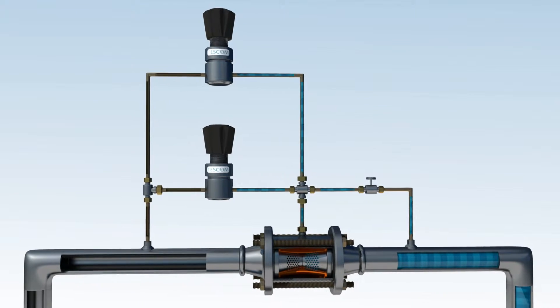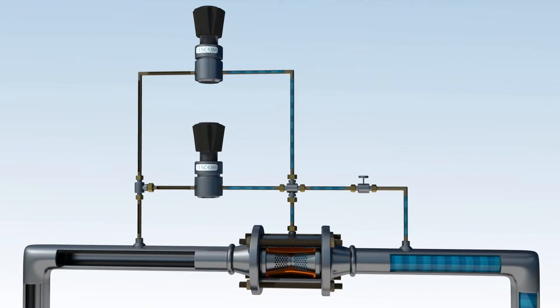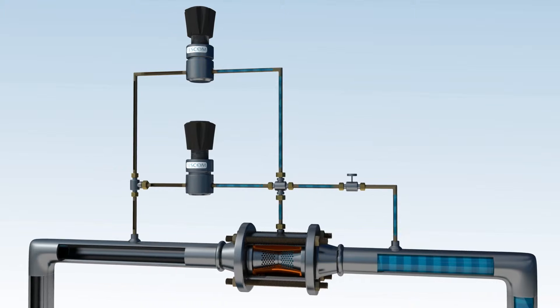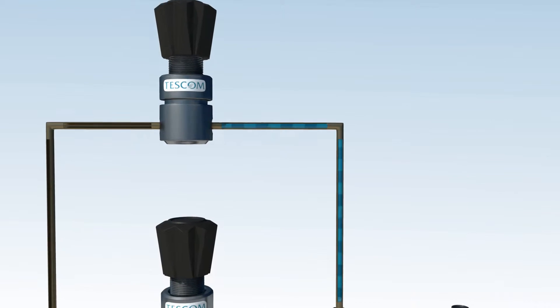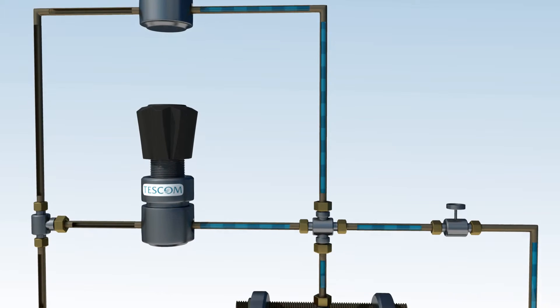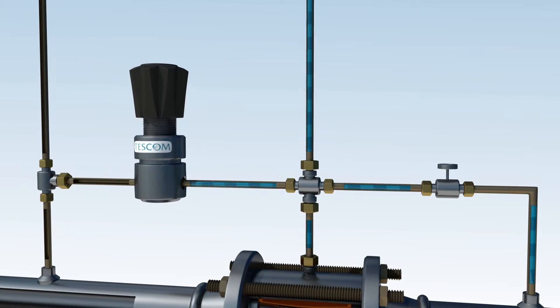SureFlow's design can control both with one valve by using a back pressure controller and a pressure reducing controller. The BPC monitors the discharge line for overpressure and the PRC monitors the suction pressure for low pressure.